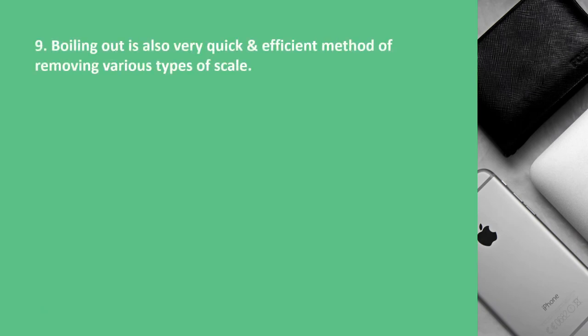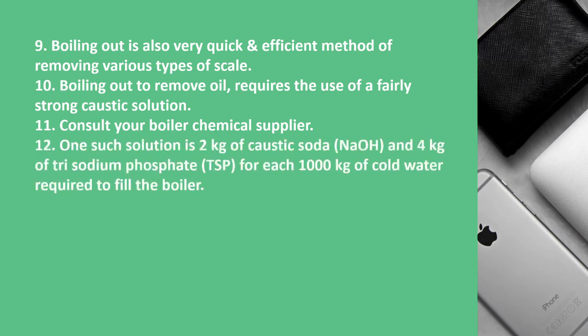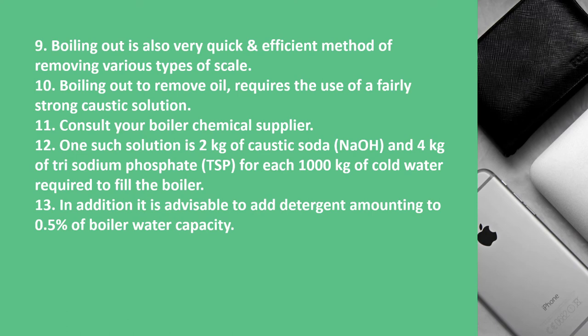Boiling out is also a very quick and efficient method of removing various types of scale. Boiling out to remove oil requires the use of a fairly strong caustic solution — consult your boiler chemical supplier and maker's advice. One such solution is 2 kg of caustic soda and 4 kg of tri sodium phosphate for each 1000 kg of cold water required to fill the boiler. In addition, it is advisable to add a detergent amounting to 0.5 percent of the boiler water capacity.